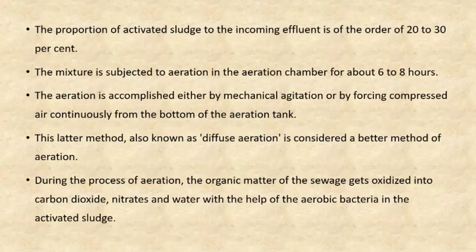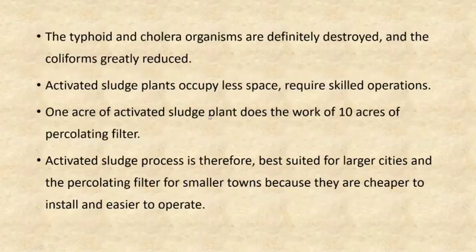This mixture is subjected to aeration in the aeration chamber for about 6 to 8 hours. The aeration is accomplished either by mechanical agitation or by forcing compressed air continuously from the bottom of the aeration tank. During this process of aeration, the organic matter of the sewage gets oxidized into carbon dioxide, nitrates and water with the help of aerobic bacteria. So till here we saw yesterday.